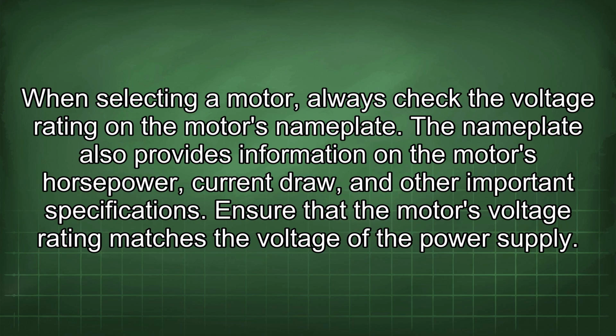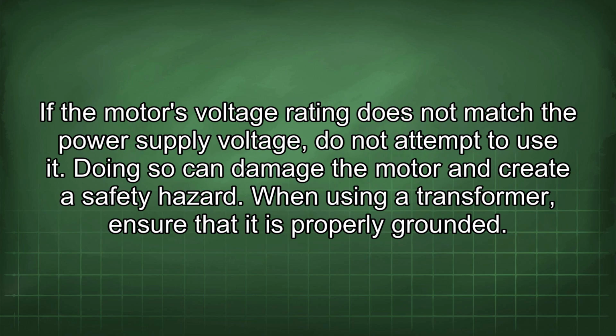When selecting a motor, always check the voltage rating on the motor's nameplate. The nameplate also provides information on the motor's horsepower, current draw, and other important specifications. Ensure that the motor's voltage rating matches the voltage of the power supply. If the motor's voltage rating does not match the power supply voltage, do not attempt to use it. Doing so can damage the motor and create a safety hazard.